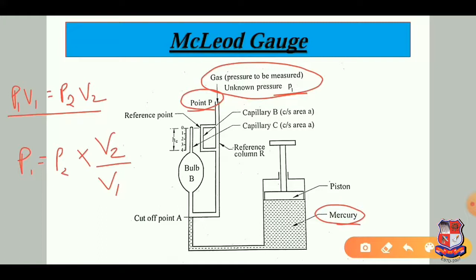The unknown pressure source P1 to be measured is connected to the gauge at point P, and the mercury level is lowered when the piston is moved up, admitting gas into bulb B. Here, when the piston is at the top position, the mercury will be at this level and this bulb will be filled with the gas, and capillary C, here, of cross section A at unknown pressure P1, when the mercury level is at cutoff level point A. Then a known volume of gas V1 is trapped in the bulb B and the capillary C.